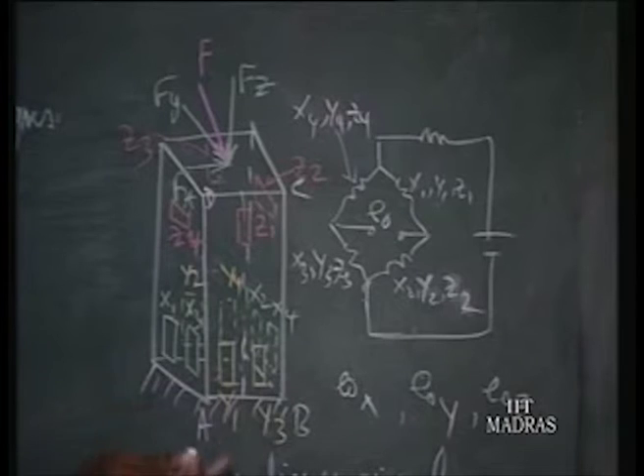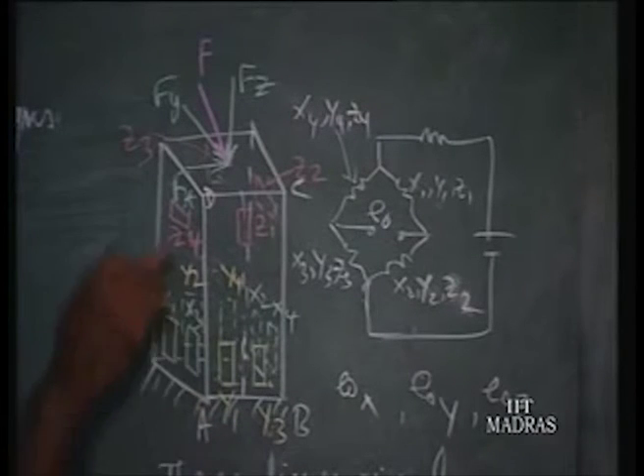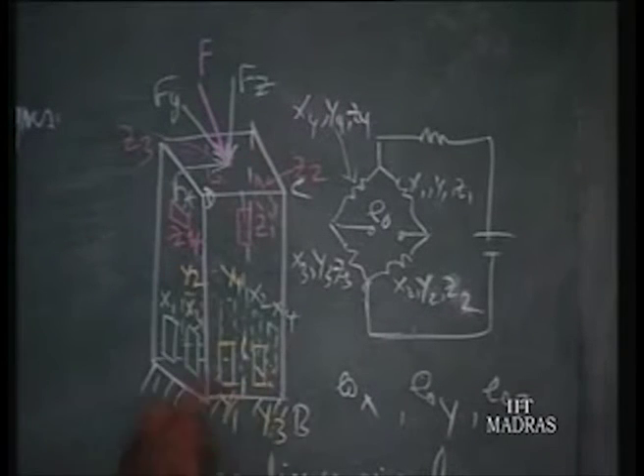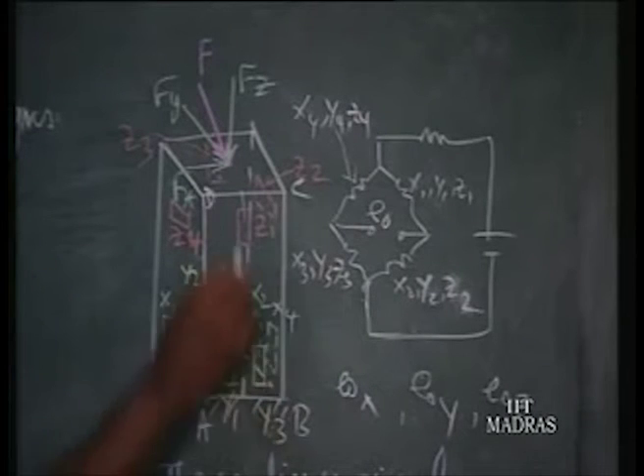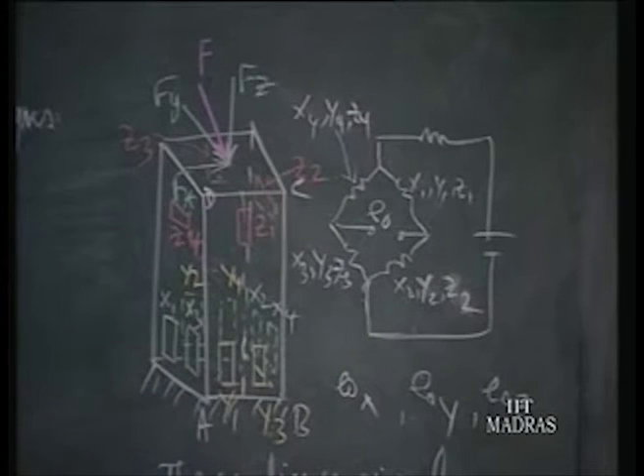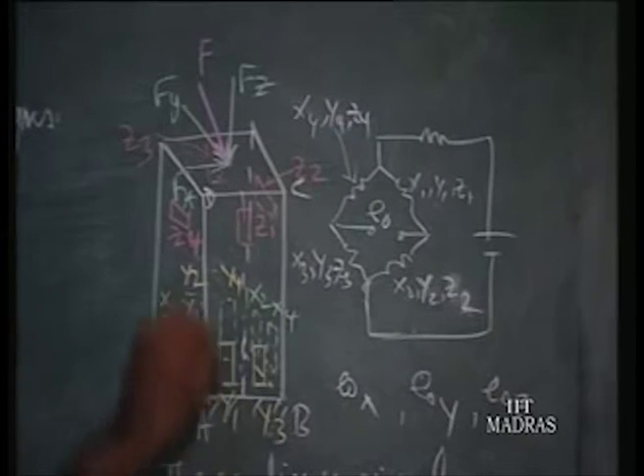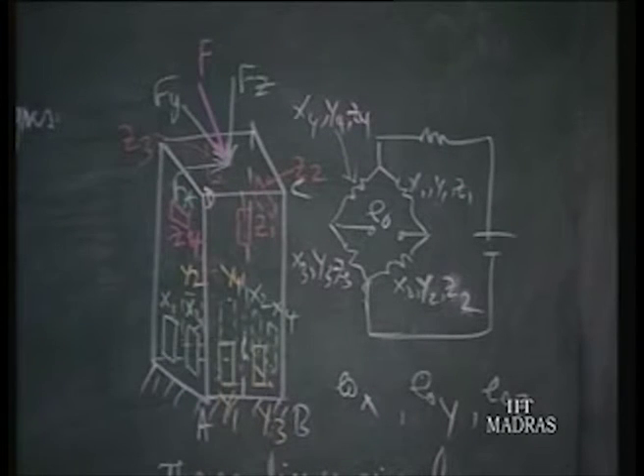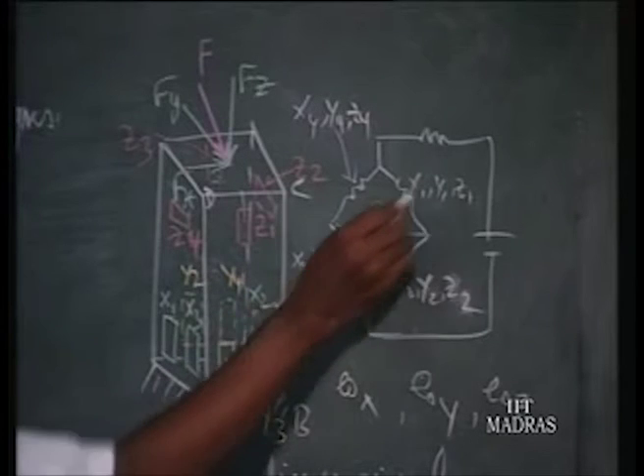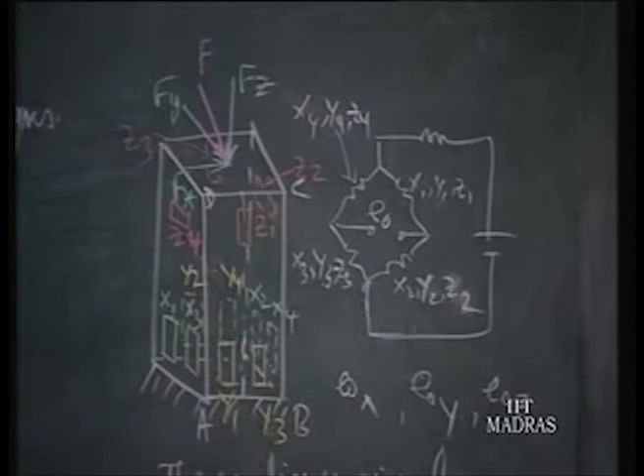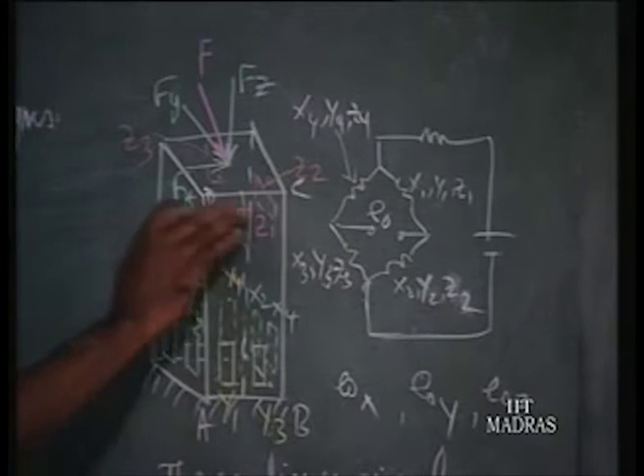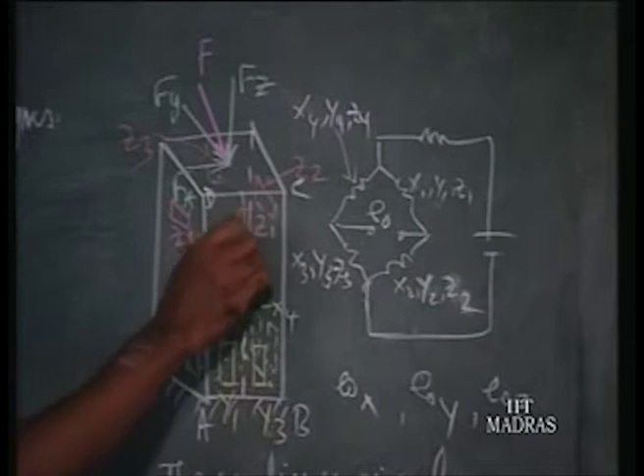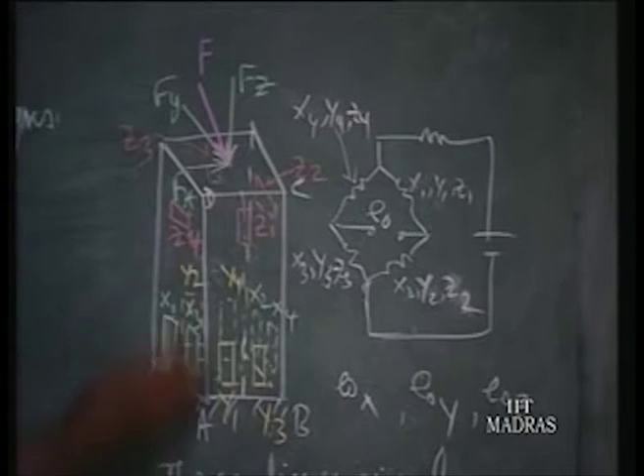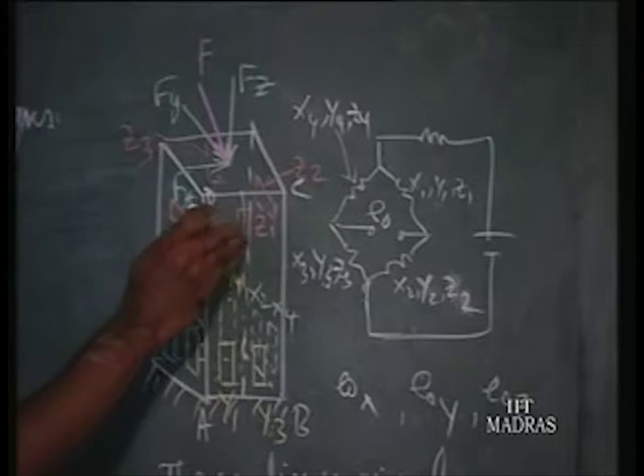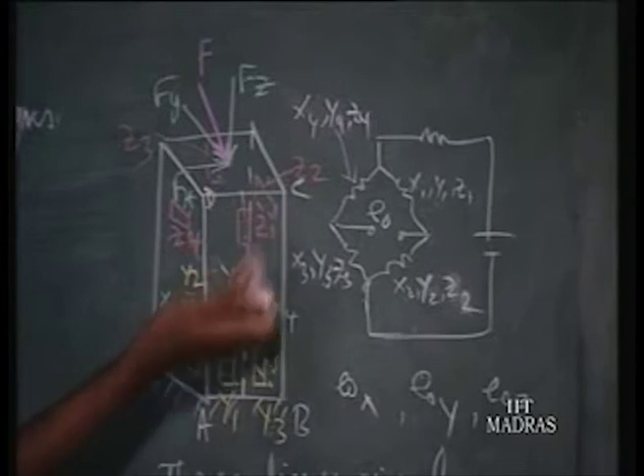For example, you can see Fy, y1, y3, and Fx is in this direction. So this is above the neutral axis. y1 will be in tension, y3 will be in compression. For Fx, y1 and y3 should be in adjacent arms, but they are in opposite arms, so the effect gets cancelled out. Similarly, you can analyze all the strain gauges. So Z1 is at the middle, and you will find the top side will be in tension, and the bottom side, from the neutral axis, in compression.